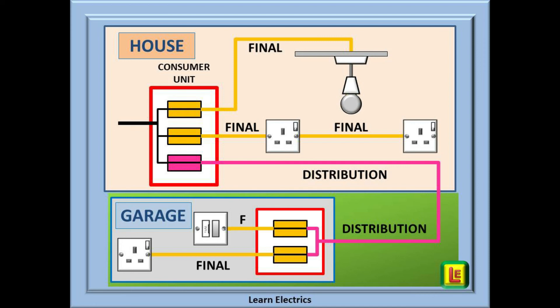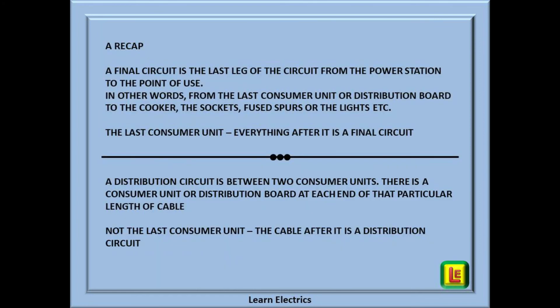Take a moment to look at this drawing — it shows very effectively the difference between final and distribution circuits. A quick recap: a final circuit is the last leg of the circuit from the power station to the point of use — in other words, from the last consumer unit or distribution board to the cooker, sockets, fused spurs, lights, etc. A distribution circuit is between two consumer units; there is a consumer unit or distribution board at each end. If it is not the last consumer unit, the cable after it is a distribution circuit.